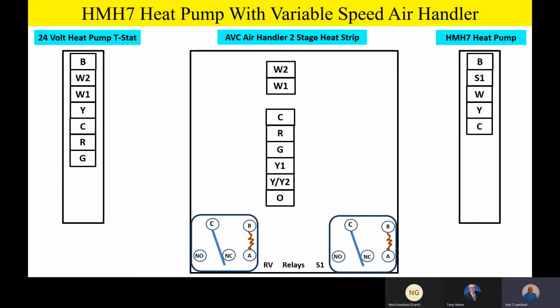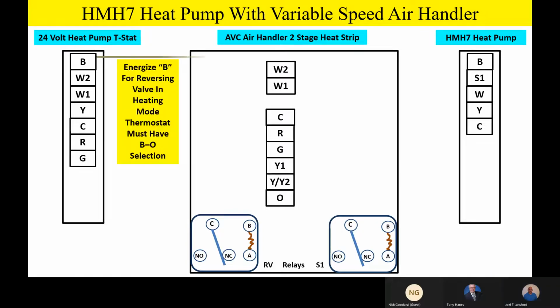Okay, here's our block diagram for just an air handler, and we will talk about some straight cooling considerations here in a few minutes, but let's just go over this with a variable speed air handler and all the functions of the variable speed air handler in the heat pump application. So the B terminal is going to go outside just like we had before to energize the reversing valve in the heating mode of operation.